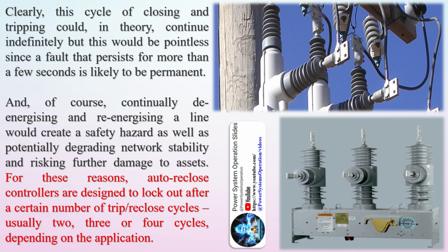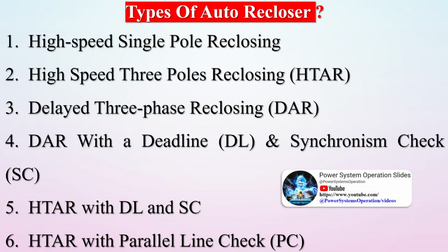If all is well, that's the end of the process, but if the fault persists, the breaker trips again and, after a further delay, the controller recloses it for a second time and checks again for the continuing presence of the fault. If the fault is still present after the second reclose, the breaker trips yet again. Clearly, this cycle of closing and tripping could, in theory, continue indefinitely, but this would be pointless since a fault that persists for more than a few seconds is likely to be permanent.